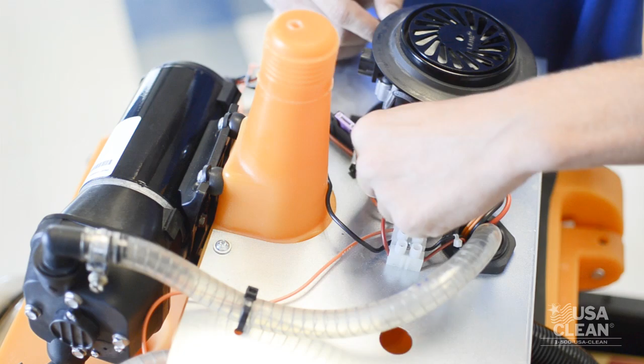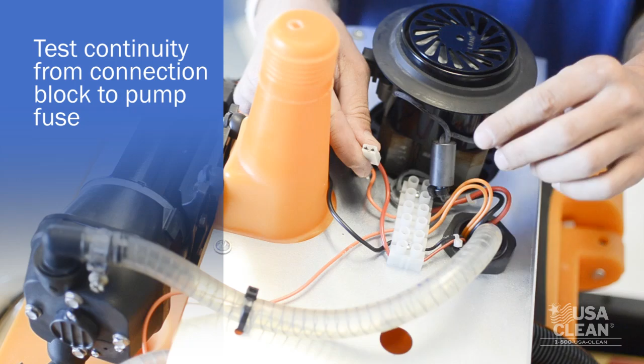So after checking the fuse and making sure your fuse is okay, the next thing we're going to do is check the line from the connector block to the fuse assembly. Now look at it and make sure there's no breaks, there's no kinks. What you want to do is unhook it from your fuse assembly. Could be a pain sometimes. Just like before, take your voltmeter and probe one end and probe the other end that's connected to the block and make sure you've got continuity in that line.